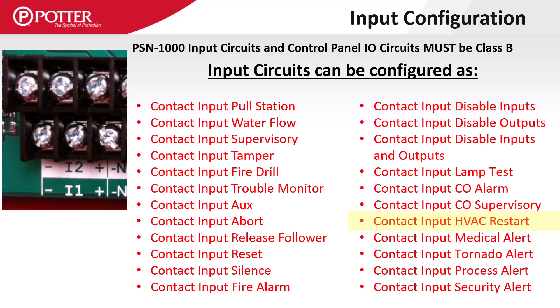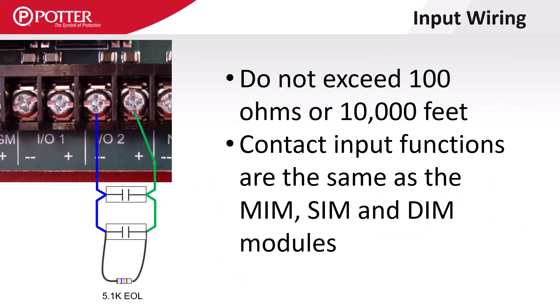HVAC Restart is used to meet New York City code requirements that HVAC units remain shut down until manually restarted. For this application, this input type is assigned to the same zone as an HVAC shutdown relay. Contact Input Alerts provide the ability to monitor ancillary devices not typically associated with fire alarms. These are the only point types that can be set to not activate the panel piezo buzzer. The limiting factor associated with any Potter IDC circuit is that it needs to be less than 100 ohms of wire resistance or less than 10,000 feet.